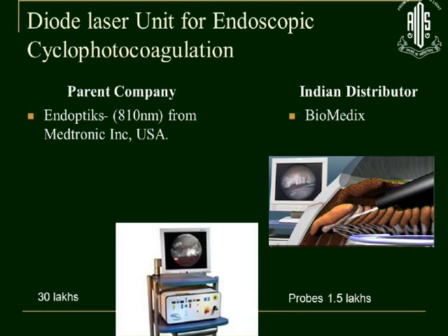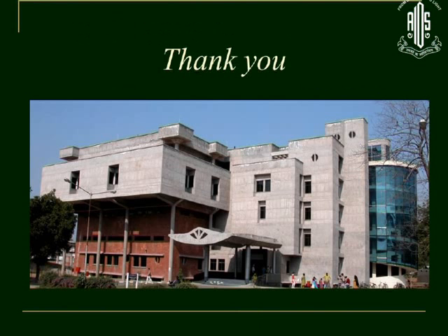And then Dr. Gauri will follow up the details of the endoscopic cyclophotocoagulation. She's giving me this figure that they've got it for 30 lakhs, but this was about 4 to 5 years ago. And this is from Medtronic Inc. and again distributed by BioMedix. Again, the probes cost about 1.5 lakhs, but she says that you can use it for about 25 to 30 patients. So that's about a nutshell for an overview of what's available in India. I think we're pretty much well stocked, and if we want to go out and do it, we just need to buy it.